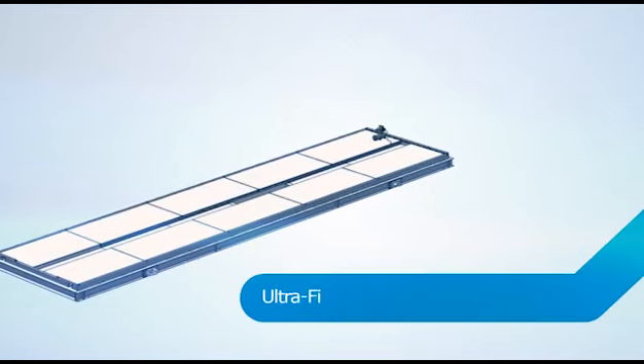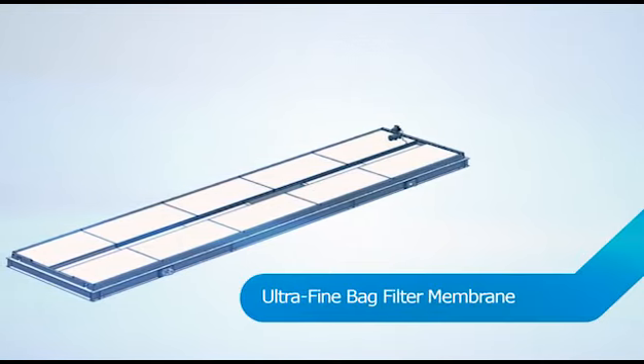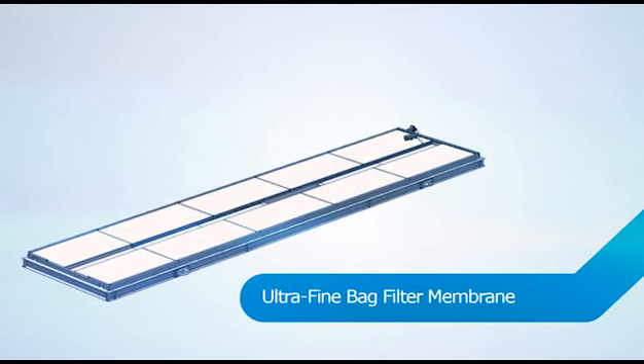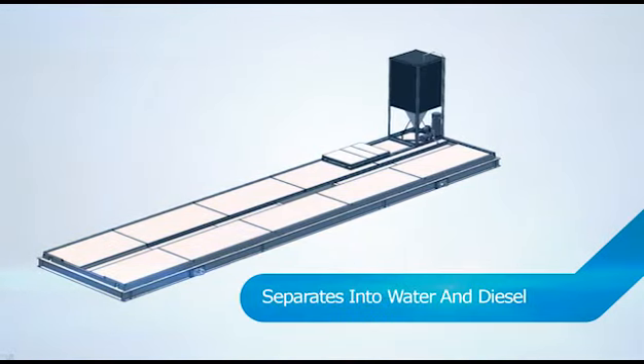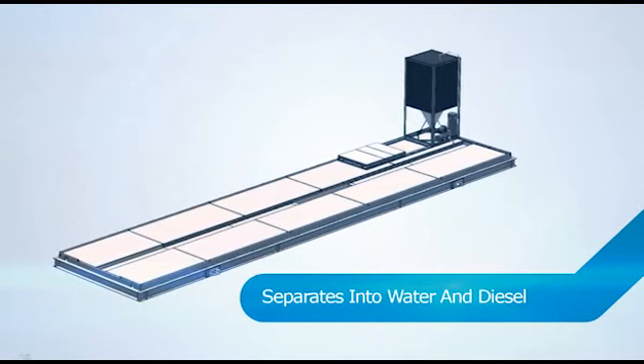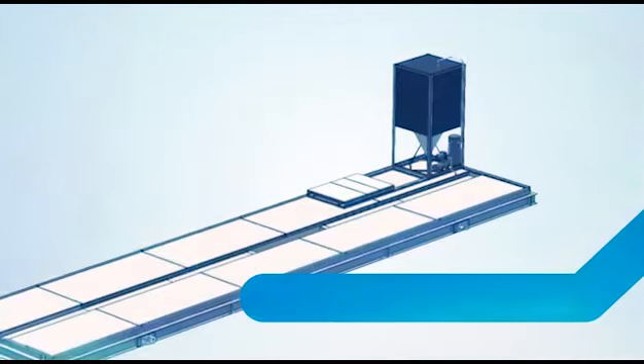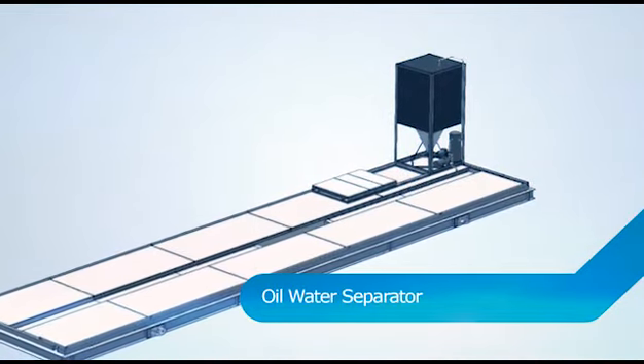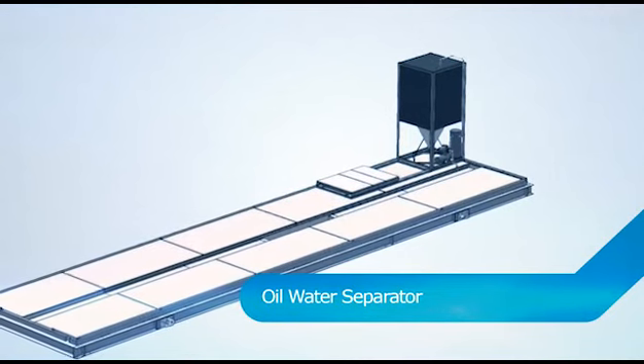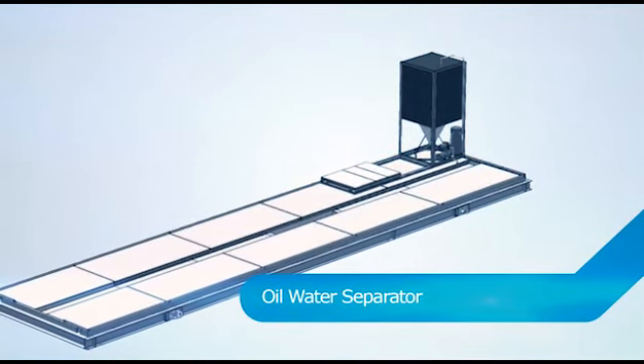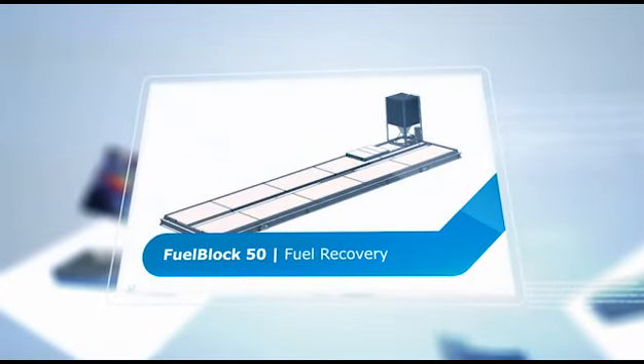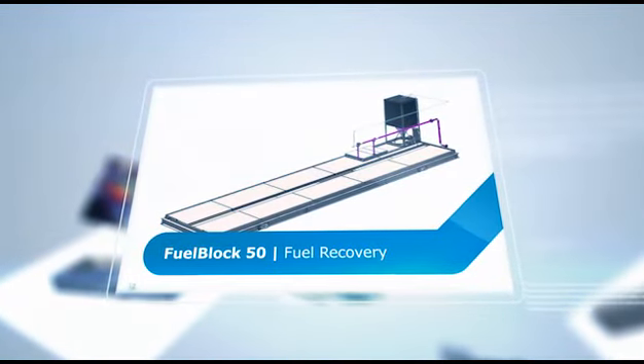The waste is pumped through an ultra-fine bag filter membrane to the 2,000 litre settling tank, where the particulate-free fluid gravity separates into water and diesel. The water phase is further treated in an oil-water separator before being discharged to the site stormwater system. The diesel phase is reprocessed by the centrifuges.